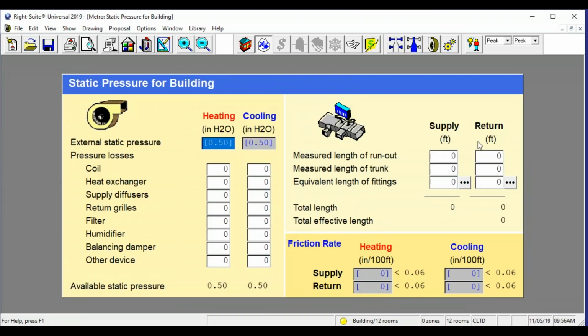we're going to set up the static pressure here. Make sure this is cool. Now with this, there's more than one way to skin a cat. Many people use different things. People will use 0.05, 0.03. I like to use 0.03. And then for the filter, let's go ahead and use 0.1.